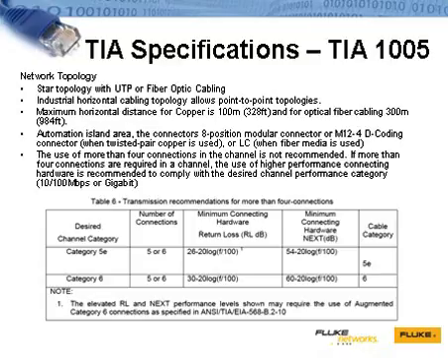practices for data communications. The TIA defines two key tests no matter the networking space, the channel or permanent link test. When a new cabling system is installed, the installation crew is typically not responsible for the patch cord or equipment cords outside of the walls. This crew pulls the cables, labels, terminates them, and certifies the performance of the permanent link, or portion of the installed cabling that's part of the permanent infrastructure in the building. The channel test, on the other hand, includes all of the permanent link plus the patch cables, and is often used to verify end-to-end data performance. The channel measurement is much more applicable to the industrial networking space.